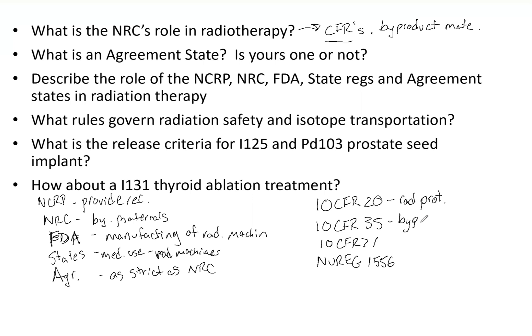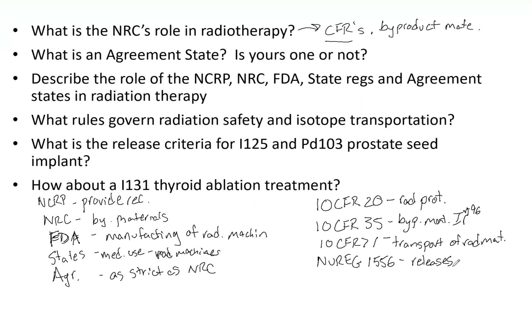10 CFR 35 covers byproduct material such as iridium and cobalt and their medical use. 10 CFR 71 covers packaging and transport of radioactive material — so when you have an HDR source and send it via FedEx, that's all based on 10 CFR 71, including dose rate or exposure rate at one meter and required signage.